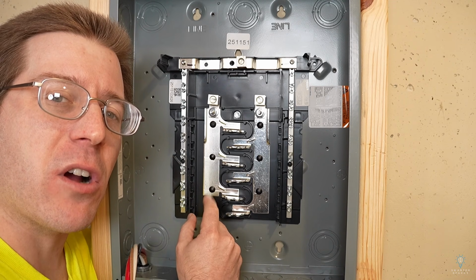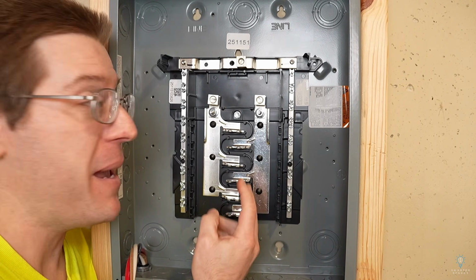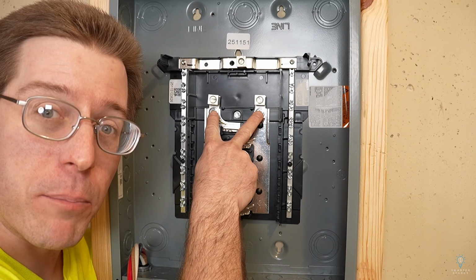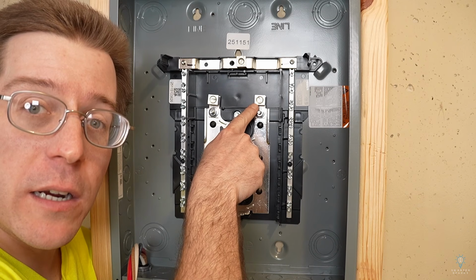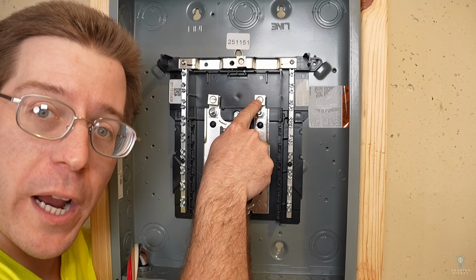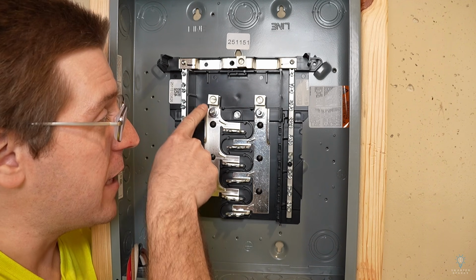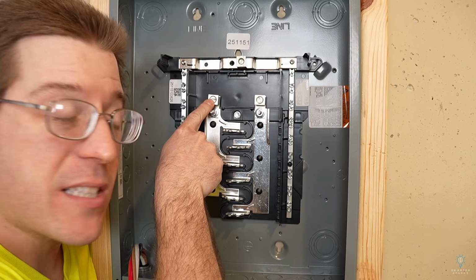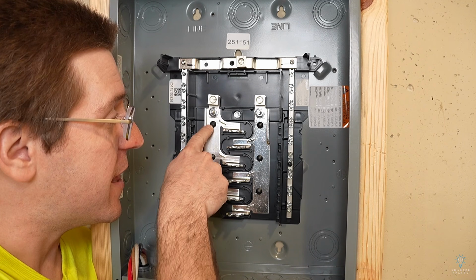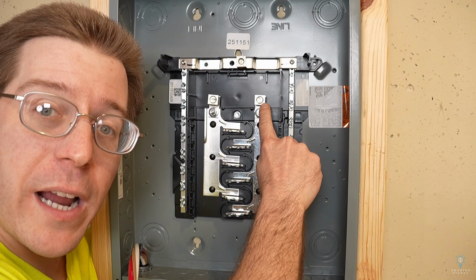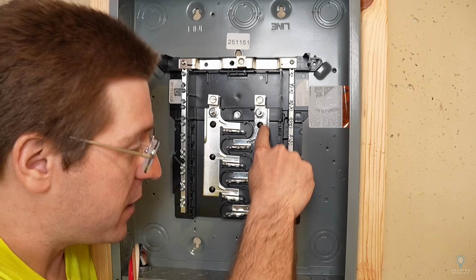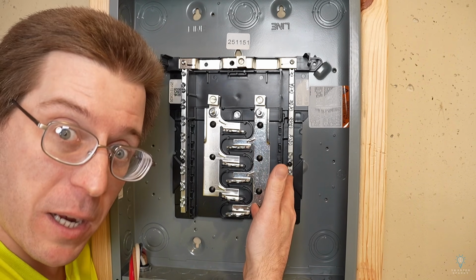Now this panel is what's called a main lug panel. Main lug meaning instead of a circuit breaker here, there's these two lugs right here that we actually just install our wire directly onto them. And as you can see, if we connect a wire to this lug, it's gonna energize this bus bar. And if we land a wire on this bus bar, it's going to energize, well, this bus bar, right?